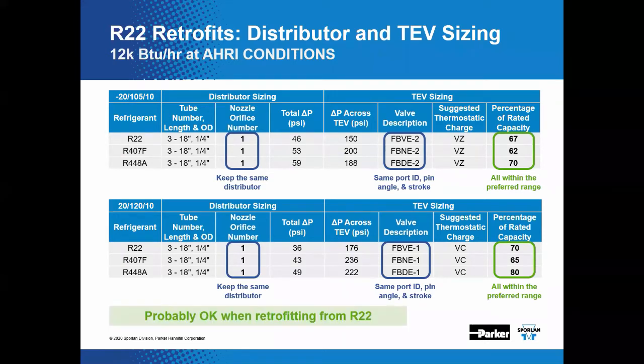In conclusion here, if we are retrofitting from R22, we're probably okay. It is still good practice to check distributor and TEV sizing. And that's really the point we're trying to make here. But we would not expect to find any serious issues. Note also that in this retrofit scenario, we can also use the same thermostatic charges on both refrigerants.